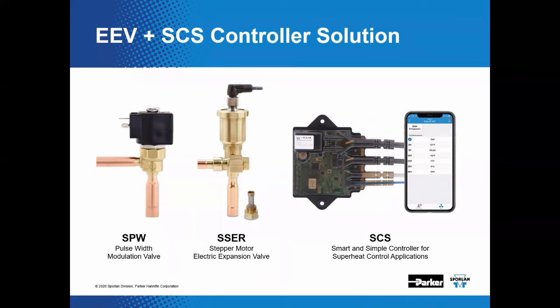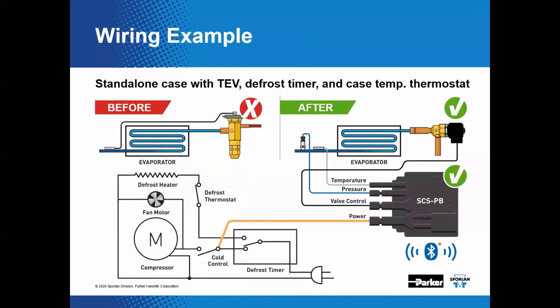The controller was also designed to have very simple setup using Sporlan's TechCheck app. So the user can quickly install and apply the solution to any superheat control application. The controller supports pulse width and stepper valve configurations, and I'll talk more about this in a few slides. To illustrate the scenario of the install, as I have shown here, this controller can be applied very easily. In this example, I have the pulse width version of the controller shown, and it can be used to replace a TEV inside of a case.